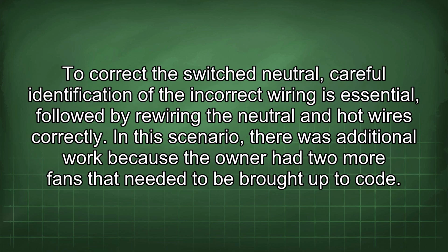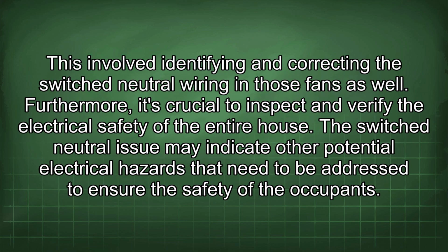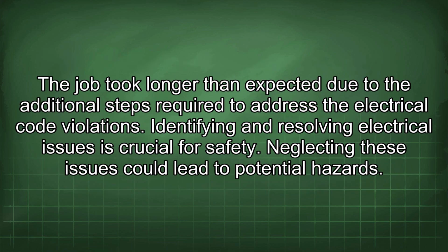To correct the switch neutral, careful identification of the incorrect wiring is essential, followed by rewiring the neutral and hot wires correctly. In this scenario, there was additional work because the owner had 2 more fans that needed to be brought up to code. This involved identifying and correcting the switch neutral wiring in those fans as well. Furthermore, it's crucial to inspect and verify the electrical safety of the entire house. The switch neutral issue may indicate other potential electrical hazards that need to be addressed to ensure the safety of the occupants. The job took longer than expected due to the additional steps required to address the electrical code violations.